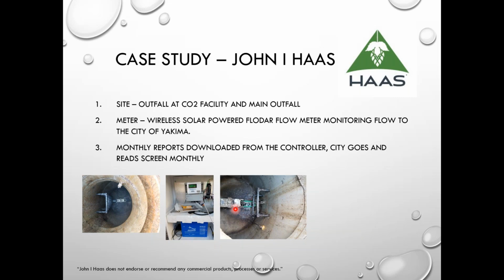The challenge that we had with this flow meter is that they wanted to make it work with an AMI system, and the Badger system that they had would take readings from a contact closure, or a relay. So we have the meter at every 100 cubic feet that it sees on total flow. It activates a relay, which then sends a signal to the Badger unit, and sends that to the city so that they can grab their flow meter data without having to go to the meter.